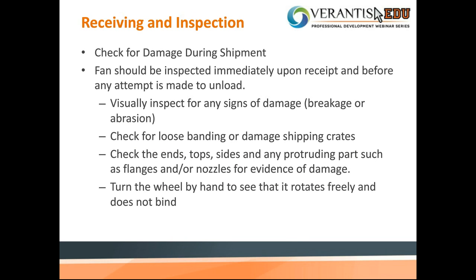So, all right, now that we've got the components out of the way with the fan, what should you do upon receiving your fan on the job site? The number one thing you need to do, before you even take it out of the crate or off the truck if you can do it then, is check for damage during shipment. Fans should be inspected immediately upon receipt and before any attempt is made to unload. You can visually inspect for signs of damage, breakage, or abrasion. Check for loose banding or damage on the shipping crates.